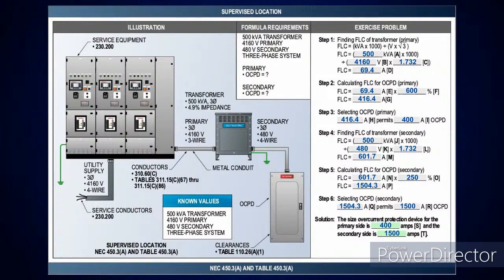Then if you look at the next one, we were not over 1,000 volts. So I come over to the far right-hand column. It tells me take it at 250% for not more than 6% impedance. And I'm going to take that 601.7 amps, the same amperage I had in the calculation before, at 250% gives me 1,504.3 amps. I didn't have a superscript, so I'm going to drop down to the next standard size per table 240.6A, which is a 1,500 amp overcurrent device. Now, you look at that, everything was the same calculation. I'm just looking at the table, looking for my superscripts, getting my percentages and doing the same calculation to size that overcurrent device.